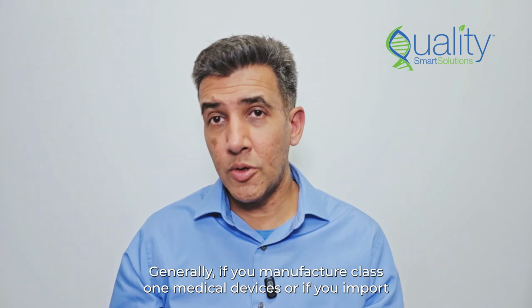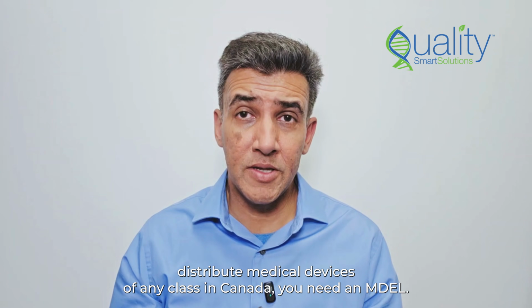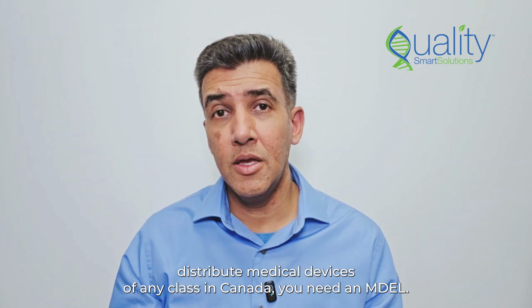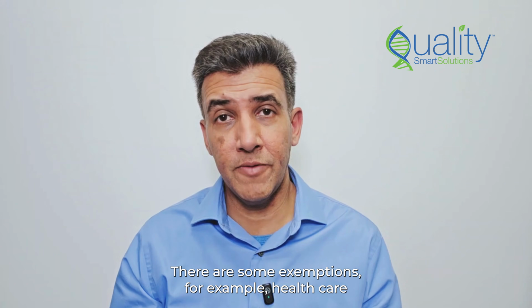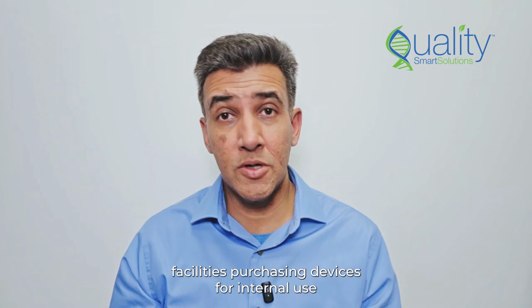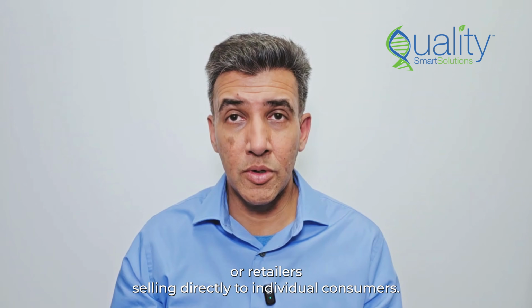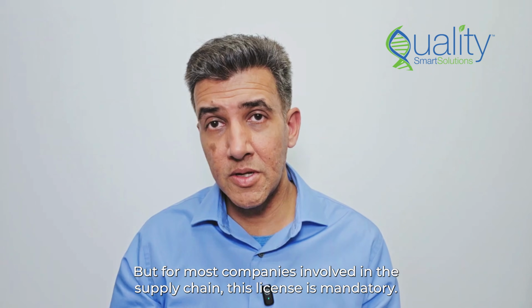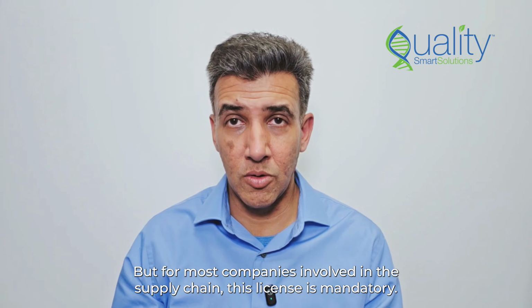Generally, if you manufacture Class 1 medical devices or if you import or distribute medical devices of any class in Canada, you need an MDEL. There are some exemptions, for example, healthcare facilities purchasing devices for internal use, or retailers selling directly to individual consumers. But for most companies involved in the supply chain, this license is mandatory.